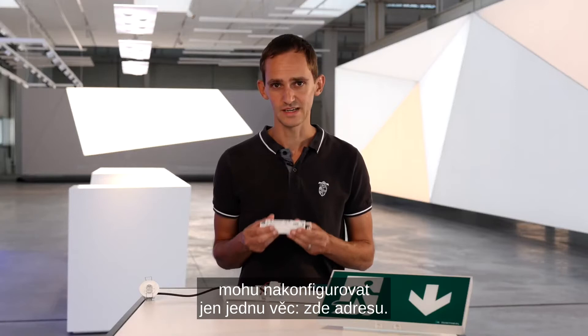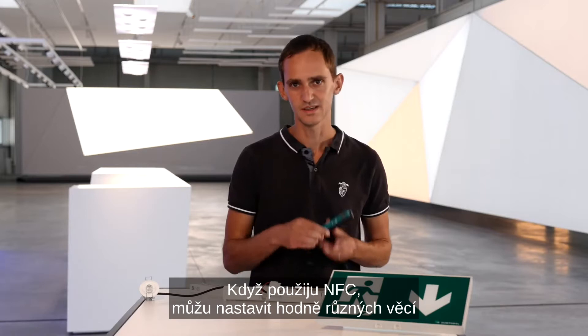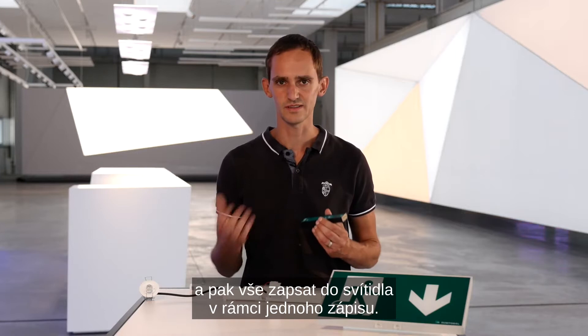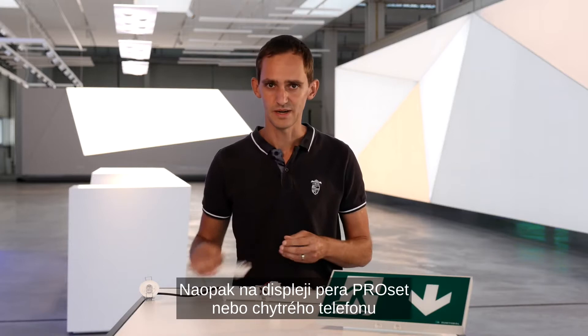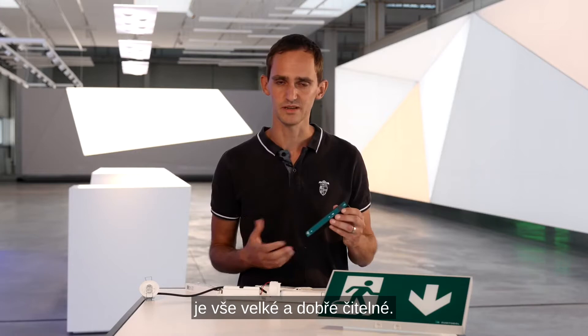One big advantage of NFC is that it is a digital interface. With physical switches I can configure just one thing — in this case, the address. If I use NFC I can configure a lot of different things and then write everything to the luminaire in just one writing process. A second advantage is that the display of the information is no longer small and difficult to read on the ballast, but big and readable on the display of the PROset pen or your smartphone.